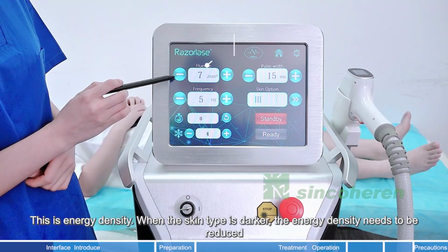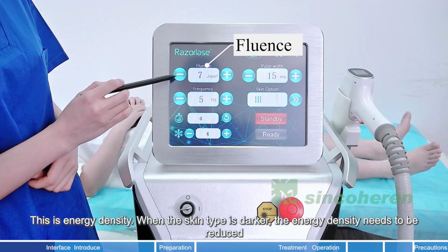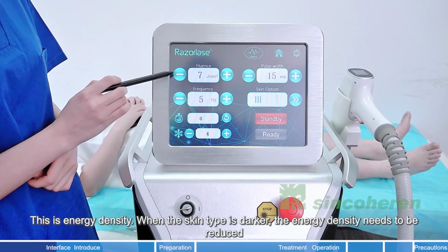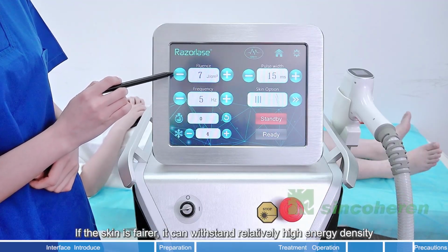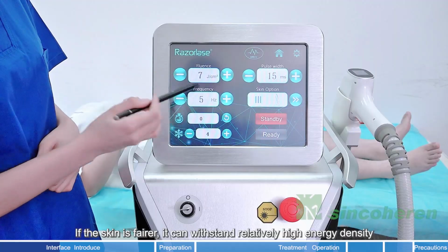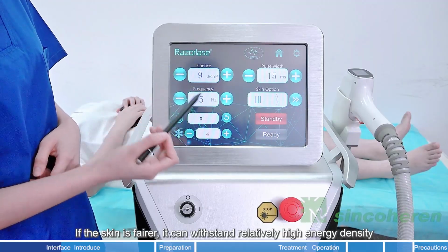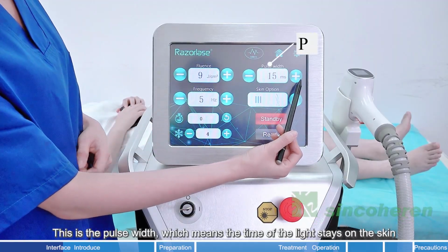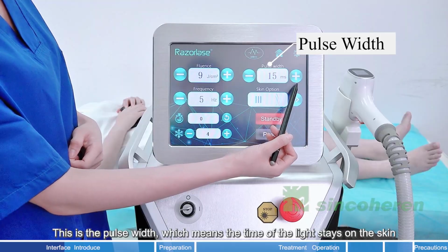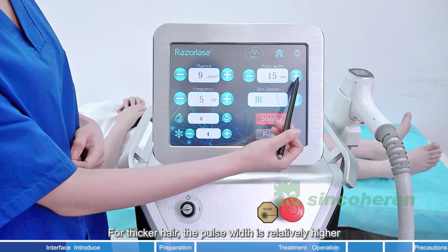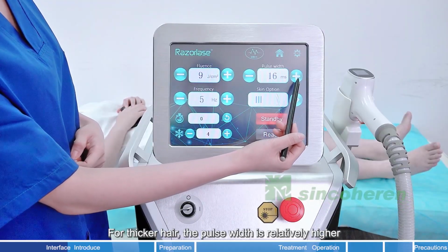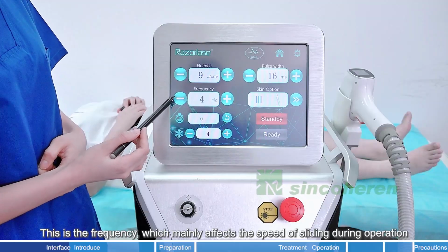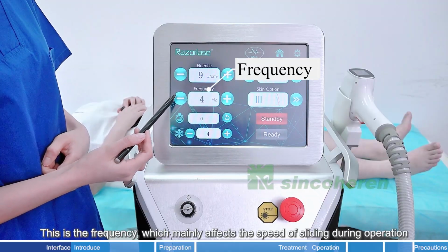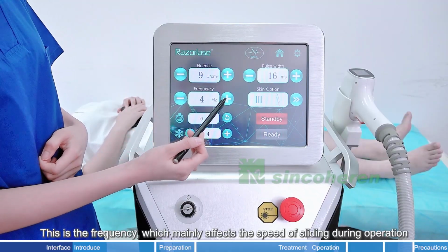This is energy density. When the skin type is darker, the energy density needs to be reduced. If the skin is fairer, it can withstand relatively high energy density. This is the pulse width, which means the time the light stays on the skin. For thicker hair, the pulse width is relatively higher. This is the frequency, which mainly affects the speed of sliding during operation.